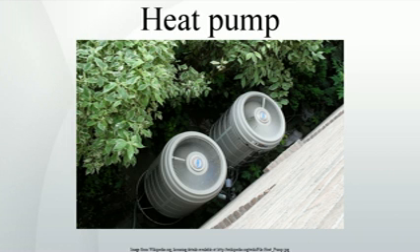Reversible heat pumps. Reversible heat pumps work in either thermal direction to provide heating or cooling to the internal space. They employ a reversing valve to reverse the flow of refrigerant from the compressor through the condenser and evaporation coils.